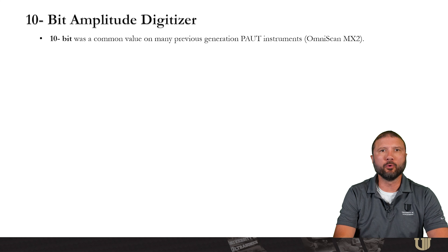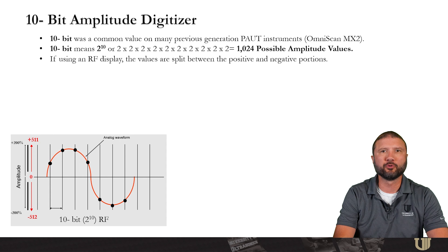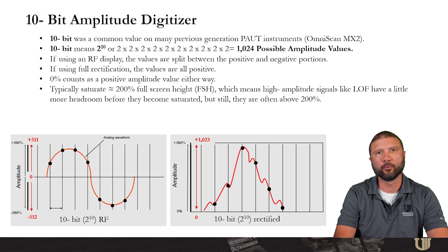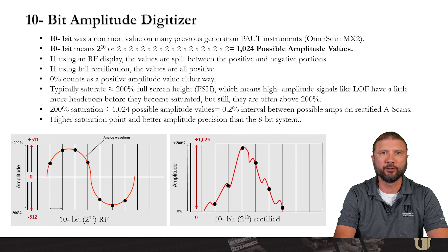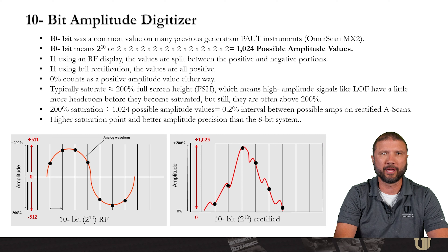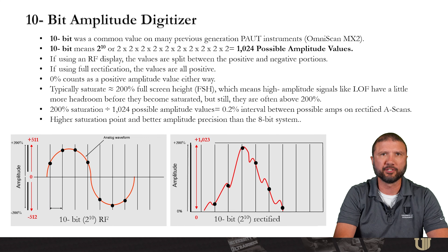10-bit was a common value on many previous generation phased array instruments, like the MX2. 10-bit means 2 to the 10th power, or 1024 possible amplitude values. If using an RF display, the values are split between the positive and negative side; using full rectification, the values are all positive, and 0% counts as a positive amplitude value either way. These typically saturate at about 200% full screen height, which means high amplitude signals like lack of fusion have a little more headroom before becoming saturated, though they are still often above 200% of screen. 200% saturation divided by 1024 possible amplitude values gives 0.2% interval between possible amplitudes on rectified A-scans — higher saturation point and better amplitude precision than an 8-bit system.